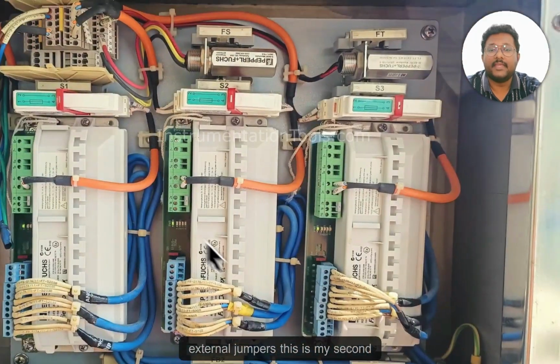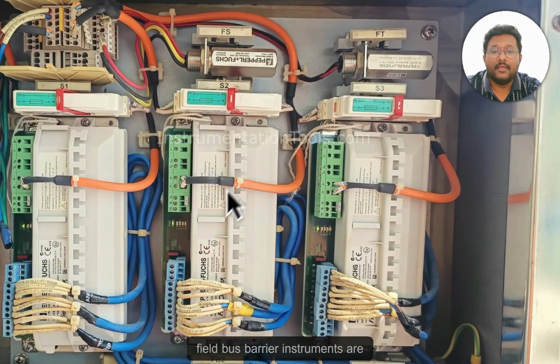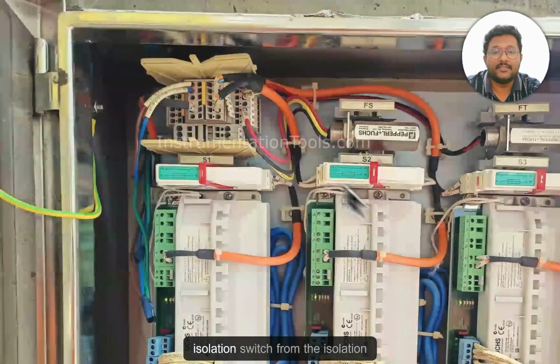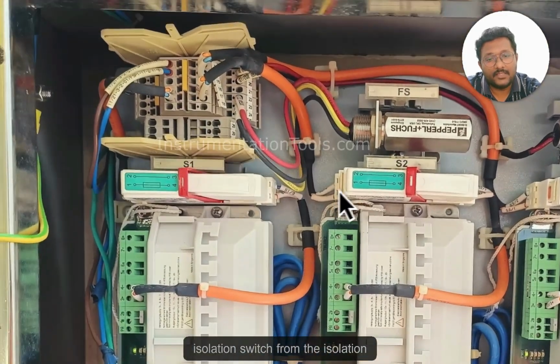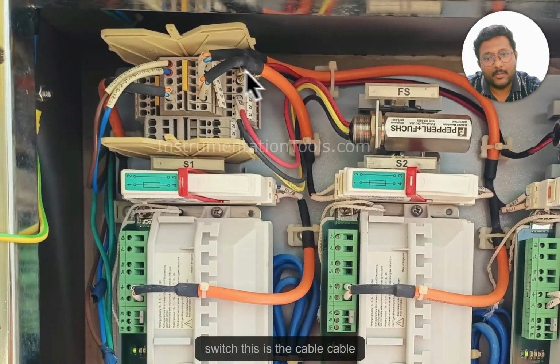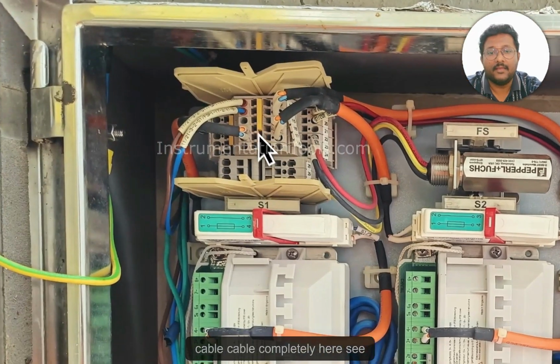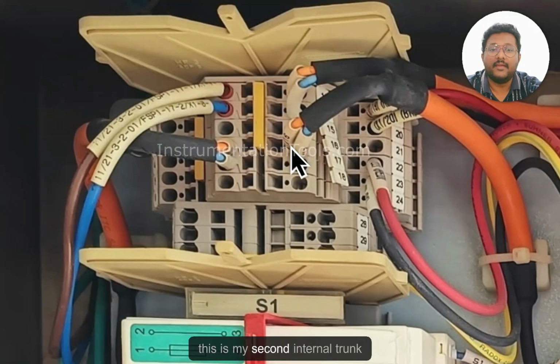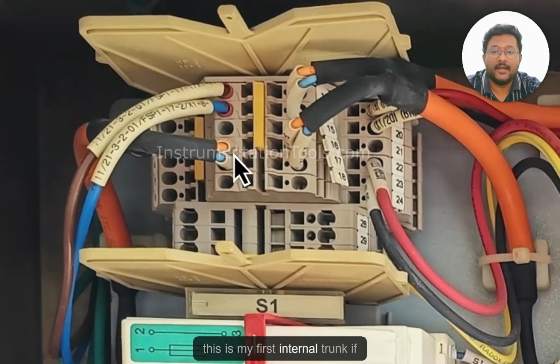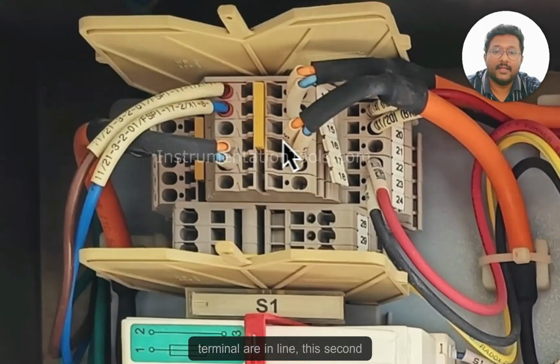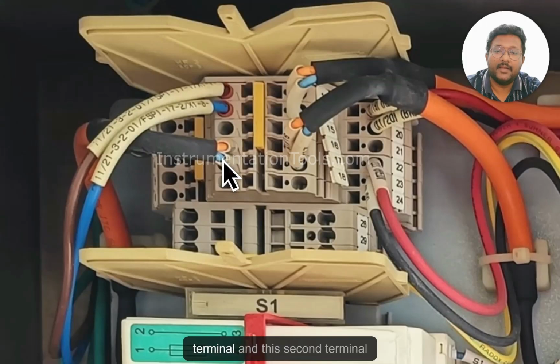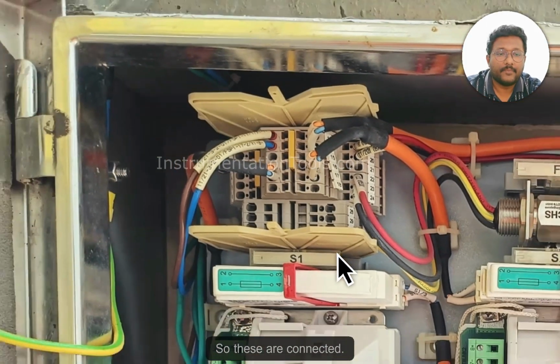This is my second field bus barrier. Instruments are connected here. Internal trunk. Again, isolation switch. From the isolation switch, this is the cable connected here. See, this is my second internal trunk. This is my first internal trunk. If you see, this first terminal and this terminal are in line. This second terminal and this second terminal are in line. So these are connected. Okay.